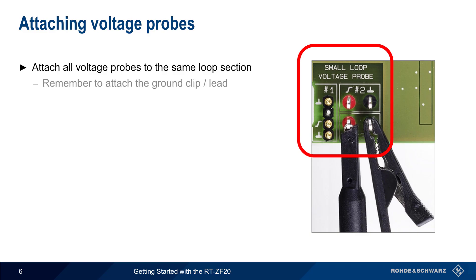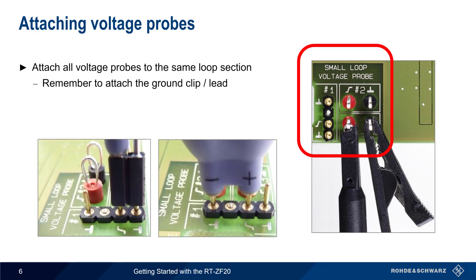And, of course, the ground clip or lead on passive probes should also be connected. Active probes can be connected to the pin headers as shown, but in some cases active probes may require a special pin adapter. Please see the probe documentation for details on specific active probe requirements.